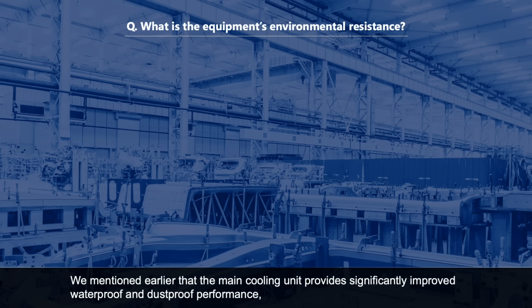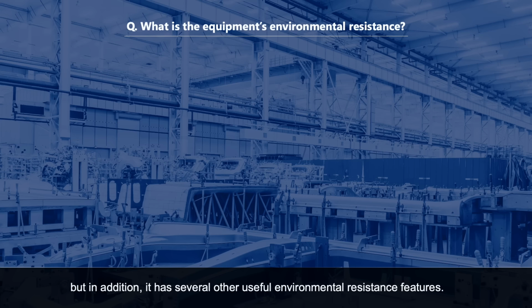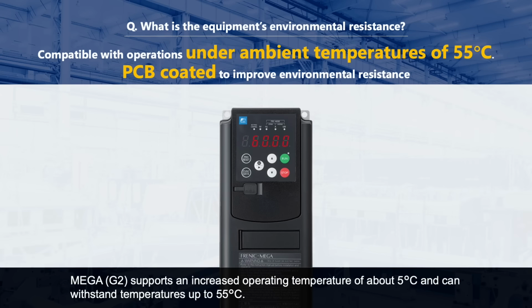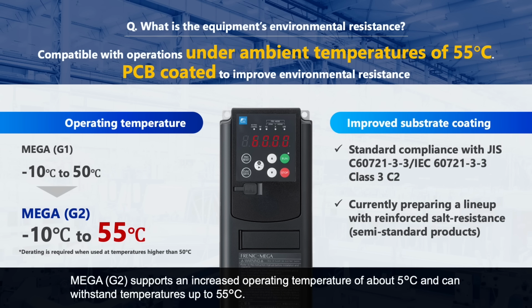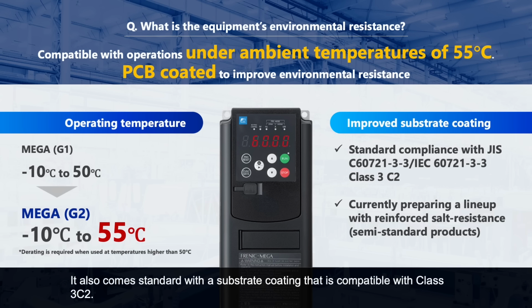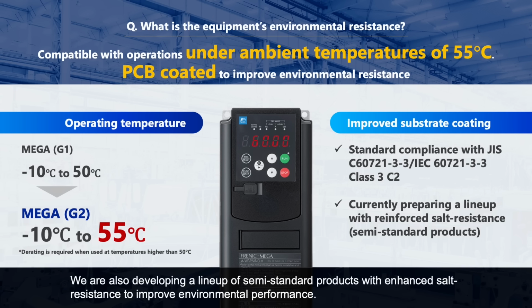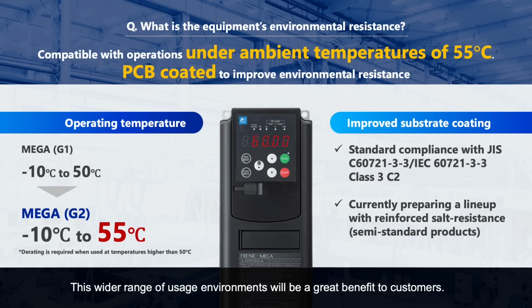We mentioned earlier that the main cooling unit provides significantly improved waterproof and dustproof performance, but in addition, it has several other useful environmental resistance features. MEGA G2 supports an increased operating temperature of about 5 degrees Celsius and can withstand temperatures up to 55 degrees Celsius. It also comes standard with a substrate coating that is compatible with Class 3 C2. We are also developing a lineup of semi-standard products with enhanced salt resistance to improve environmental performance. This wider range of usage environments will be a great benefit to customers.